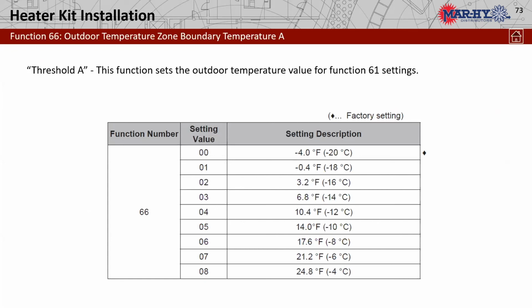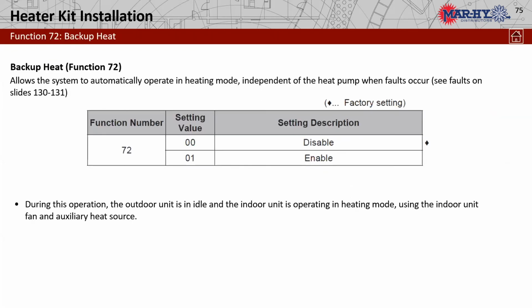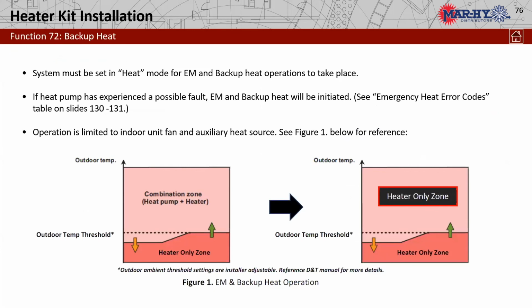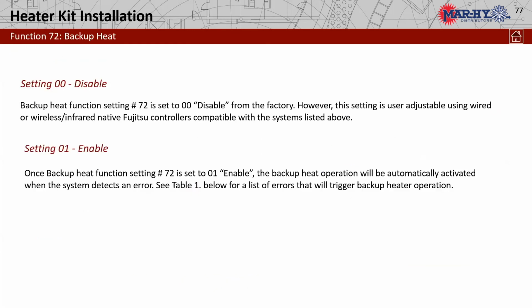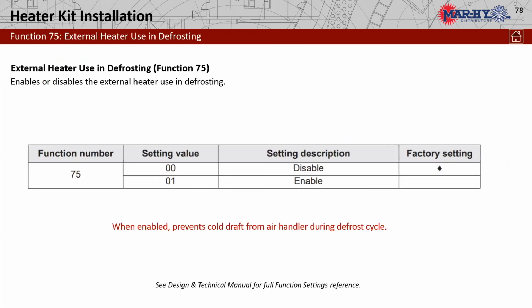Setting 61, there again, that's our heat pump lockout. I think we've been through this. Backup heat zone, 00 on your backup heat is a disable. 01 is enabled. This is what it looks like on that external heater used for defrost, enabled.